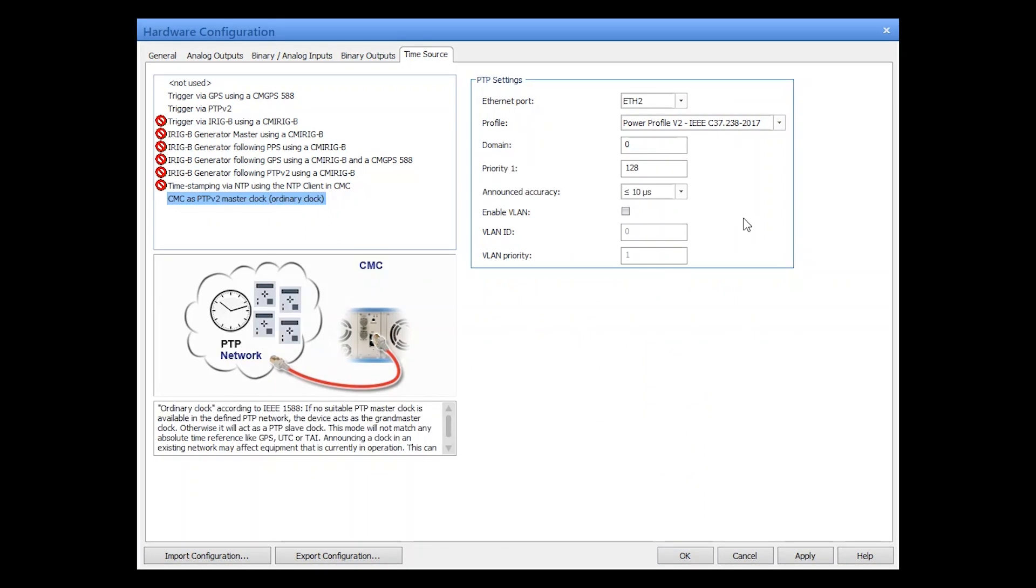The CMC can also be used to simulate the grandmaster clock with TestUniverse. However, the CMC behaves like an ordinary clock. That means if no suitable PTP grandmaster clock is available in the network, the CMC acts as the grandmaster clock. Otherwise, it will act as a PTP slave clock.